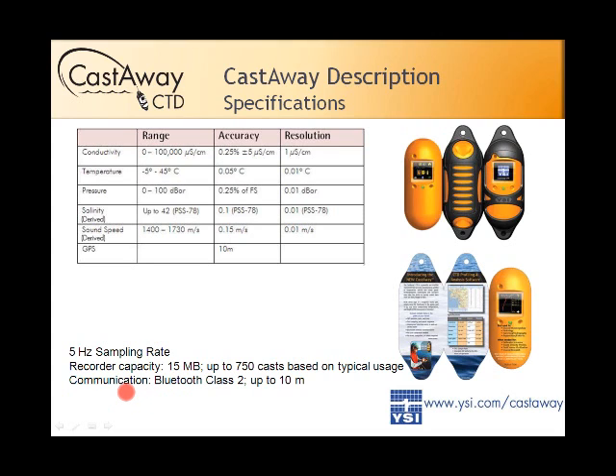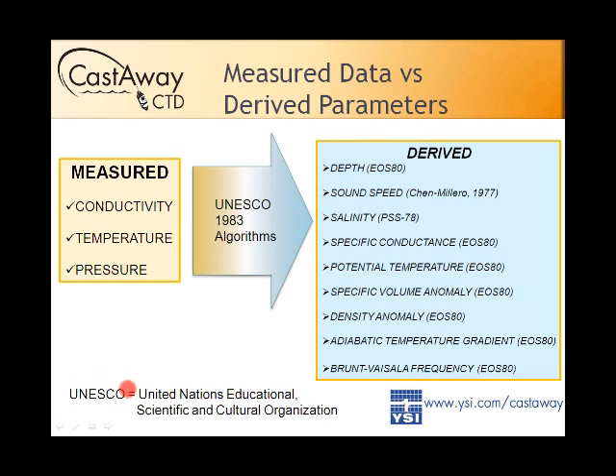The Bluetooth communication range: we put a nominal range of 10 meters on it. In an open room or outdoors with no interference, you may get 20 or 30 meters out of it. The device is a conductivity, temperature, and depth instrument — directly measuring pressure, temperature, and conductivity, with all other outputs derived by calculations, which is standard in the industry.